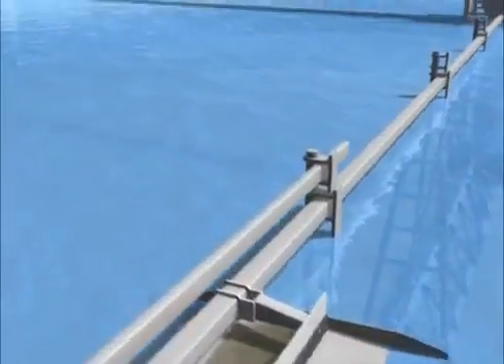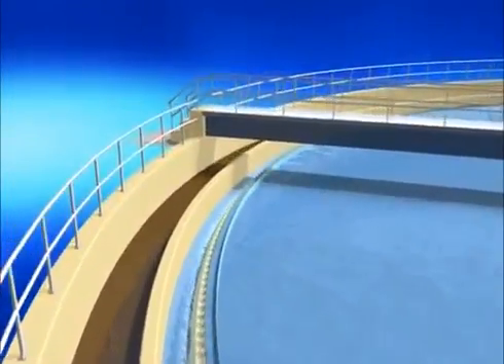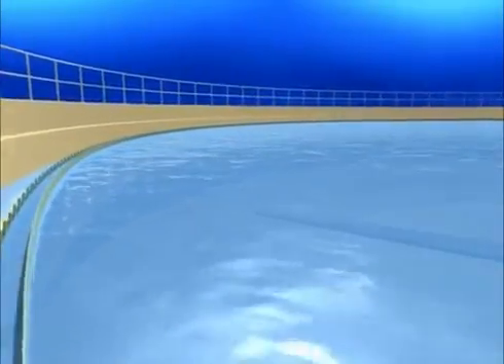The low influent flow velocities combined with an effective use of the cross-sectional area of the tank allow solids to separate and settle. Short-circuiting is prevented because of the position of the inlet flow in relationship to the effluent weirs. Solids that settle on the basin floor are collected across the entire area and removed by the Tobro unitube header. The key to successful solids removal is the design of the header. The unitube header configuration is based upon a sophisticated hydraulic model. Critical to the design are the header shape and orifice coefficients. This design was modeled by a special university study and field verified.